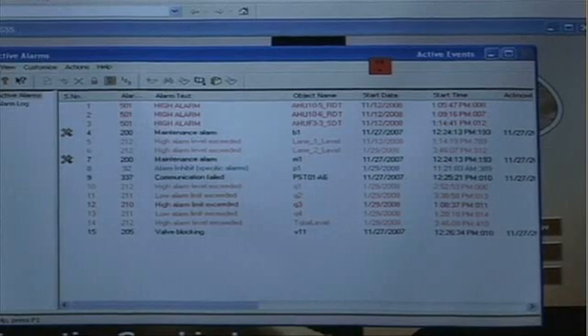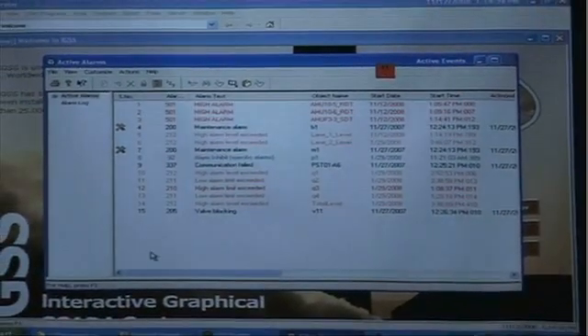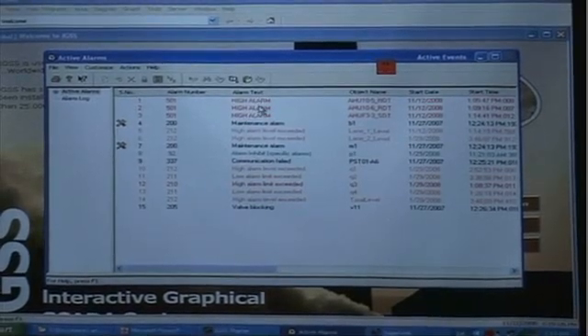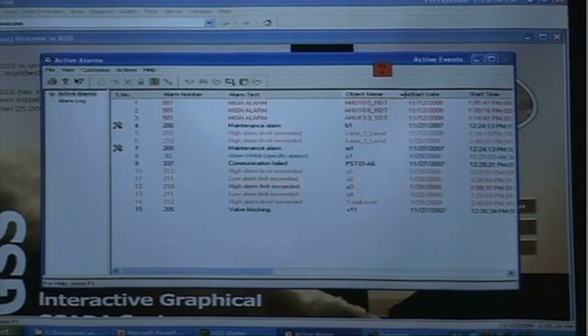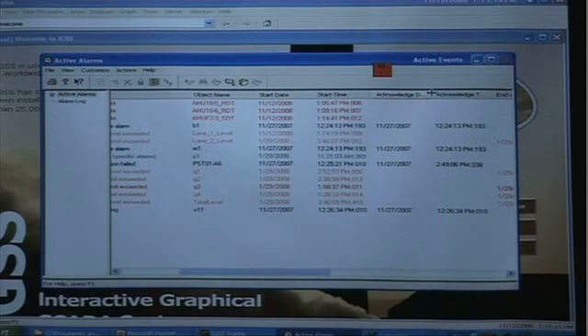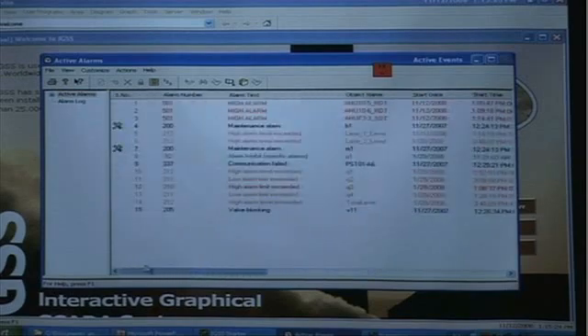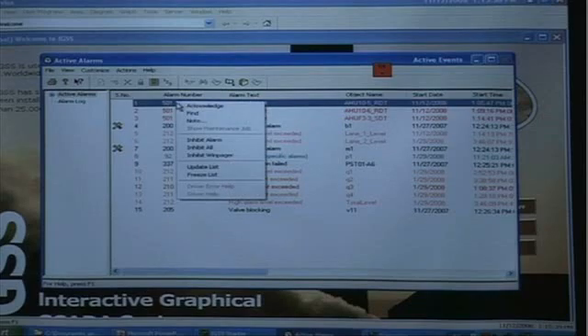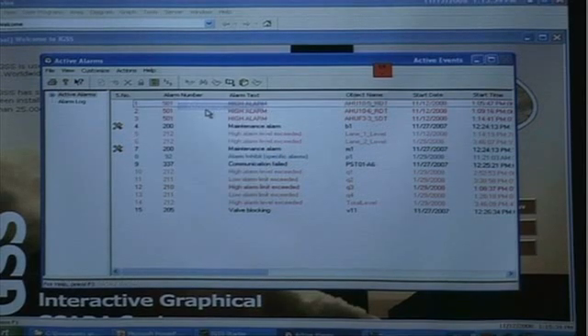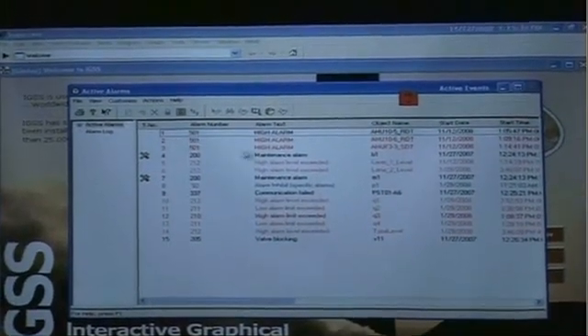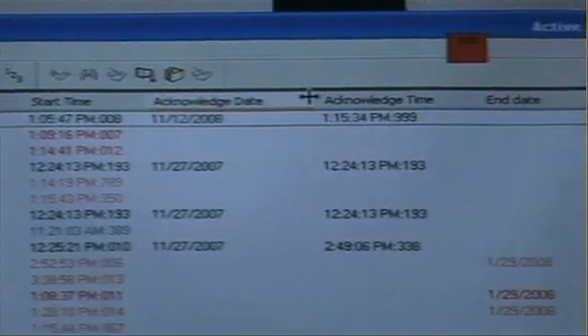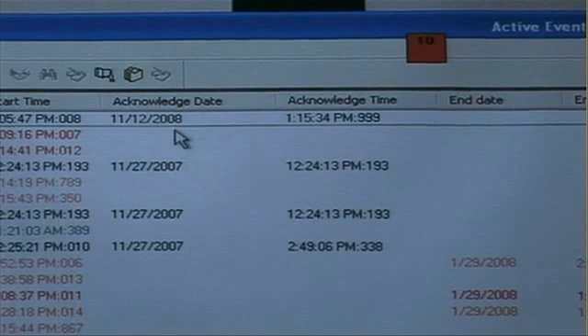The alarm list is divided into columns. I have a sequence number on the left telling me the order in which alarms have arrived, an alarm number, an alarm text which tells me the cause of the alarm, and the object name of the object issuing the alarm. I have a start date and start time, and an acknowledge date and acknowledge time. I can acknowledge alarms from the active alarm list by right-clicking and choosing Acknowledge. Notice it changes color, indicating acknowledgement has been accepted, and under Acknowledge Date and Acknowledge Time I have a timestamp telling me when the acknowledgement occurred.